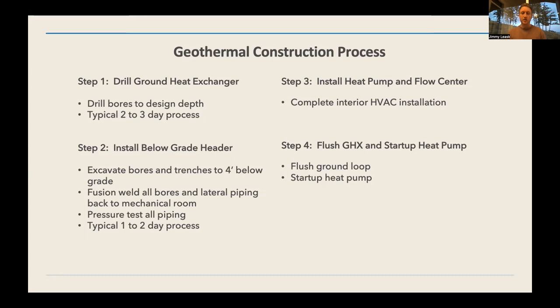And then at the very end, we make sure it's flushed. The ground loop needs to be flushed and purged of all its air. There is a 20% propylene glycol mixture. Since it's operating at different temperatures, it does get below freezing sometimes, so the propylene glycol is essentially an antifreeze for the water running through the pipe. Then the heat pump gets started up and you're able to heat and cool your home through that one box, through the geo exchange system.